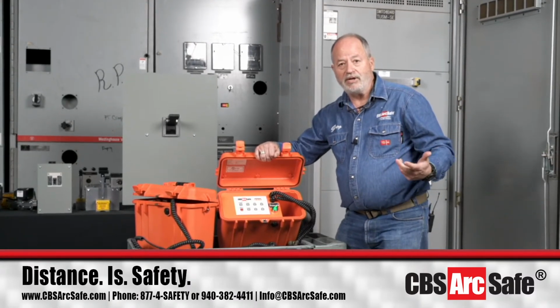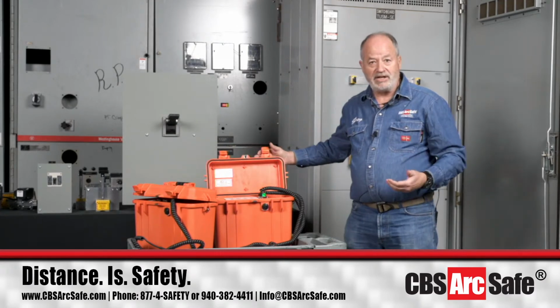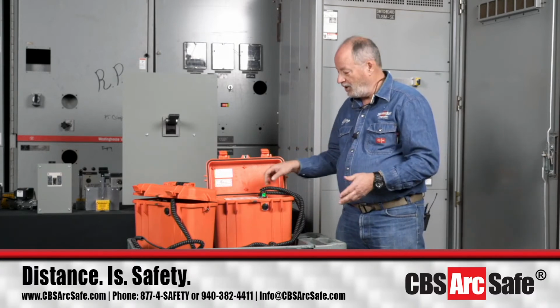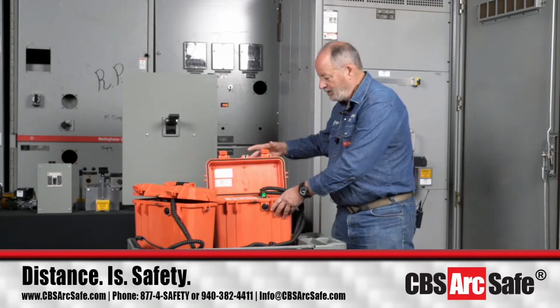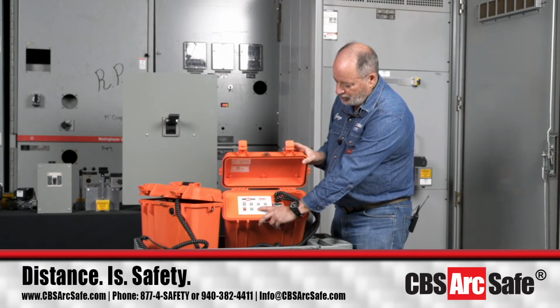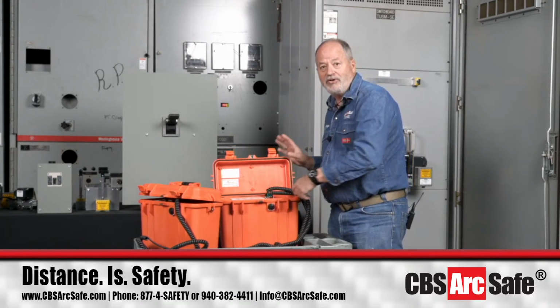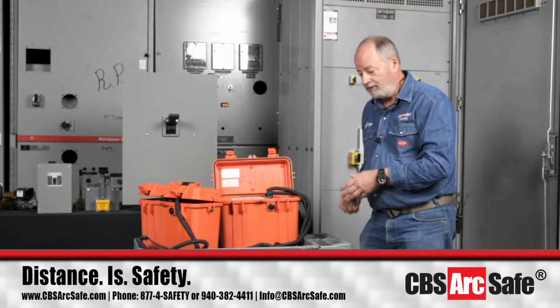Every time you operate the RSA, turn the RSA on first to make sure you've got the proper settings for the breaker you're going to use it on. When you turn it off, it will remember the settings. I've just turned it off and back on, and if we go look, you'll see it has just the settings that I put in. It's not a volatile memory that's going to disappear. It'll remember the last set of things that you put in there.